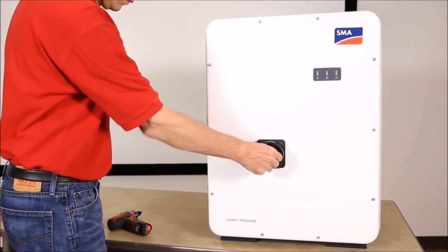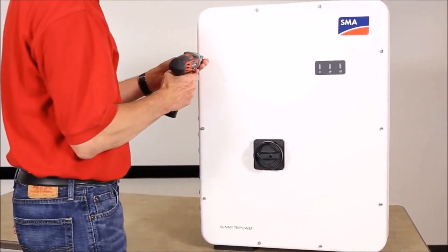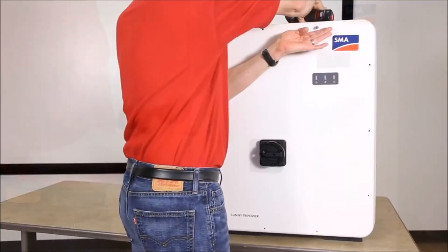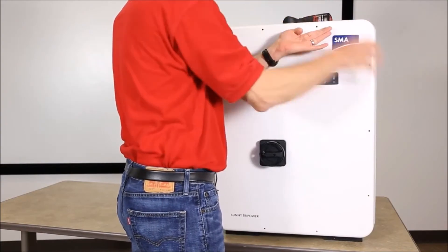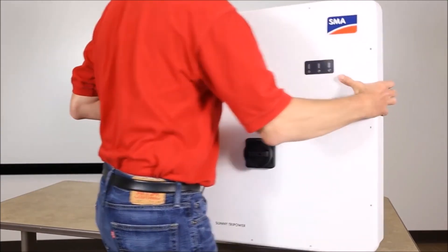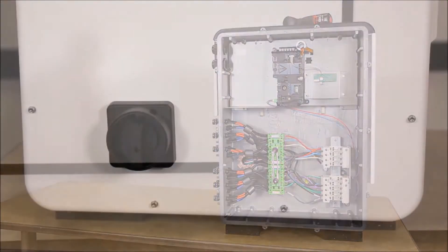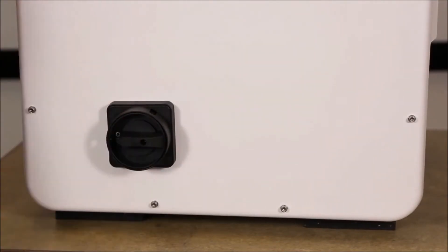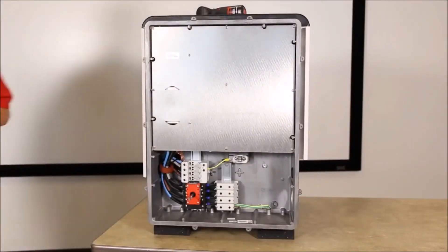The next step is to remove the covers of the inverter off of both the DC and AC sides. Each cover has 10 Torx 25 screws securing it. For clarity, for the rest of this video, we will not show conduit connections to the body of the inverter, but ensure that conduit and fittings appropriate for the install location are installed correctly.